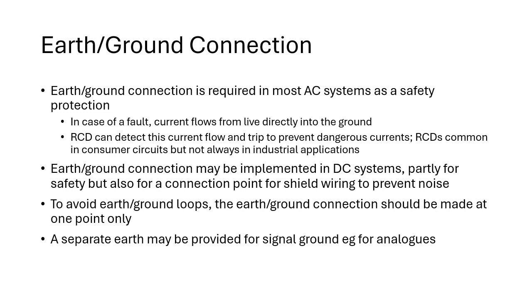Now, it is important, particularly in industrial systems, to avoid earth or ground loops. You should only make the earth or ground connection at one point. Otherwise, you can actually end up with two earths which may be at different potentials, and then you can get a current flow between them, which can cause its own problems. So for example, that may overcome some electronic devices. I've seen two panels side by side which weren't correctly earthed, and there was a potential difference of 100 volts between them. So one, that was dangerous. It was strong enough that you could feel it electrically. You could certainly measure it using a multimeter. And that 100 volts might be high enough to overcome a 24 volt or an analog circuit and cause damage to that circuit. So you need to make sure that those devices are connected, but it needs to be a central connection only. Often you provide that connection via one big terminal, and then there's a star connection, and you wire everything to that one terminal through that sort of star arrangement.